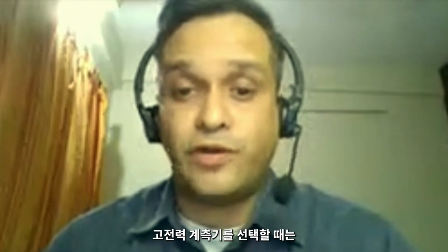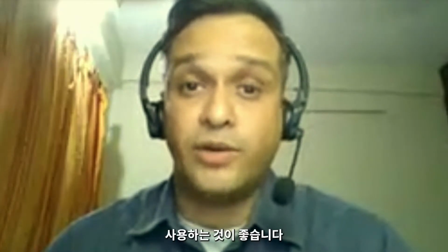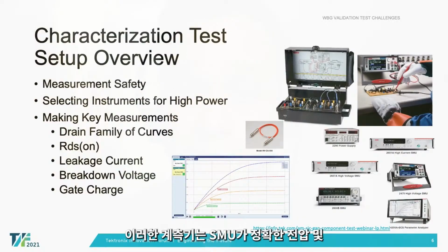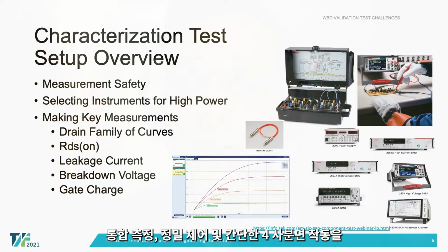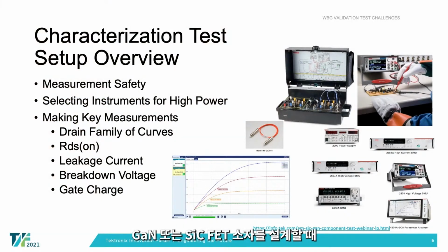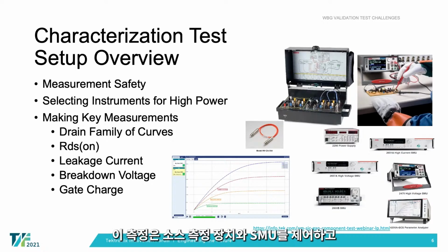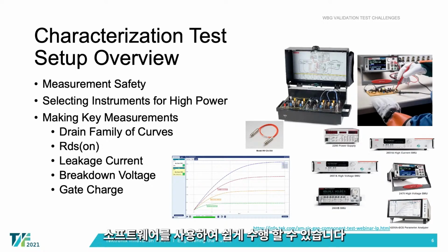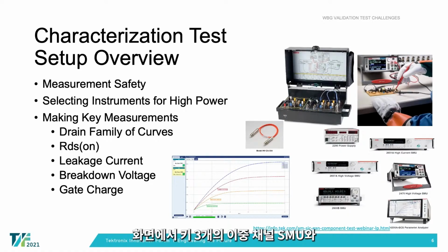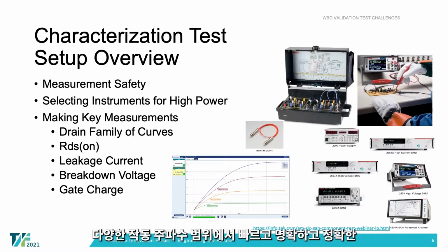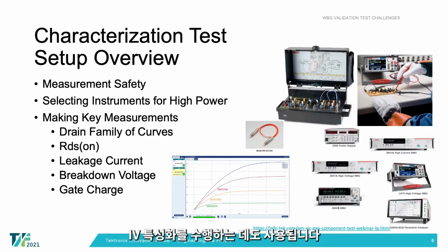When it comes to selecting instruments for high power, it's recommended to use instruments like source measure units, SMUs. These instruments provide integrated measurements, precise control, and a simple 4-quadrant operation where the SMU can source or sink precise voltage and current signals. When designing GaN or SiC FET devices, the main characteristic is to measure the family of curves. This measurement can easily be performed using source measure units and software that can control the SMUs and graph the curves. On the screen, you will see one such image of the curves performed using the Keithley dual channel SMUs and the Kickstart software. An instrument such as a parametric analyzer is also used to quickly get parametric insights and perform fast and clear, accurate IV characterization across different operating frequency range.